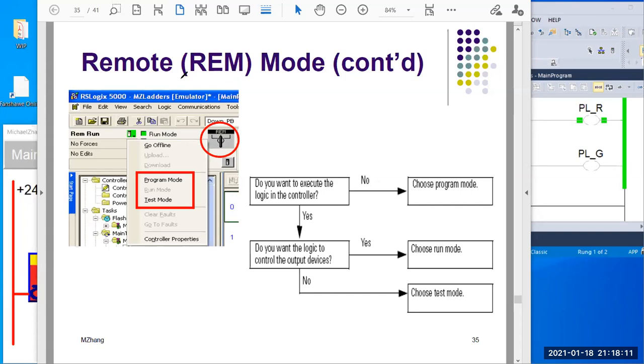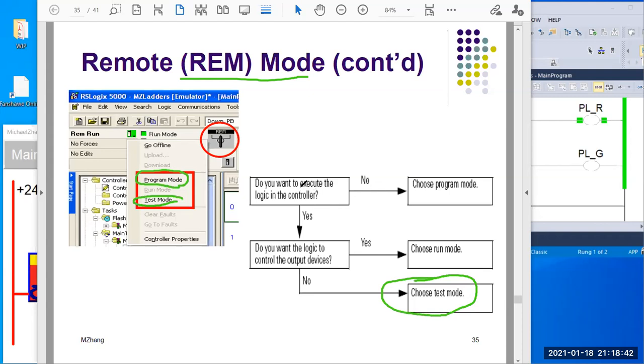With remote mode, you have more choices. You can have program mode — if you're in program mode, it's just like you flip the switch into program mode. You also have a test mode. Test mode means you want to execute logic, but you don't want to energize the output local devices. So you can choose test mode — that's a very nice feature if you want to test your program.